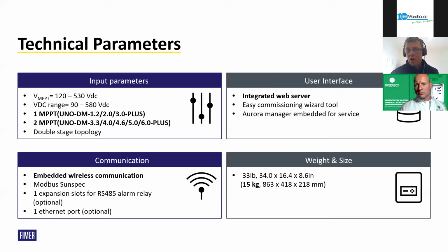It has an integrated web server, which I'll show a little more about very soon — easy to connect, easy to work with. It shows real-time functions on both the AC and DC sides, and production. It has embedded wireless built-in, Modbus Sunspec for Modbus RTU and Modbus TCP. There are a couple of optional COM kits needed when connecting an energy meter through RS485, as well as for running a connection to the internet via Ethernet if there's no Wi-Fi available on site, but I'll show you that very soon.